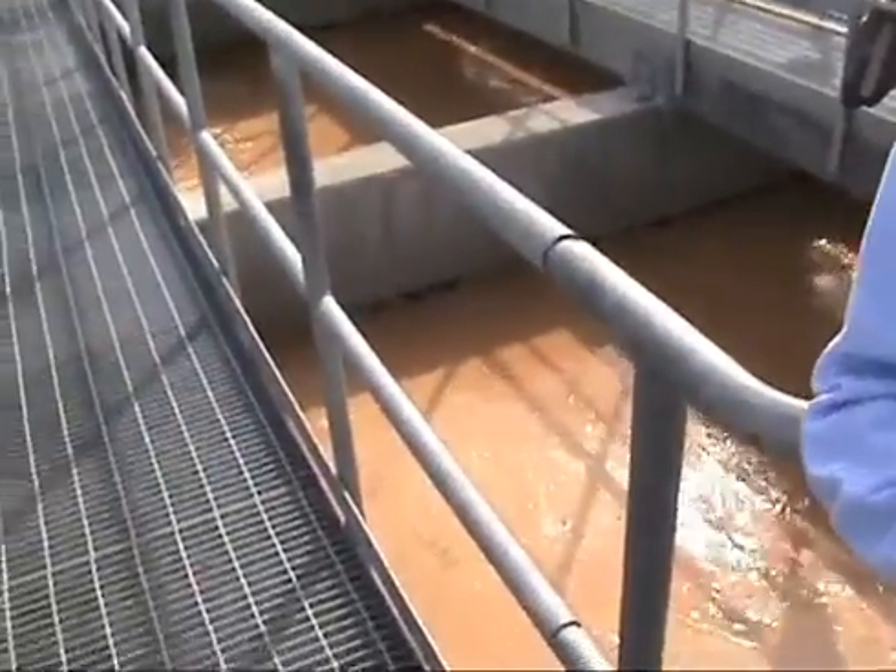And, Frank, we were talking about your ability here at the wastewater treatment plant to recycle water from the aeration basin back into the anoxic zone. Can you kind of go through that process with us? What's powerful about this treatment system is it takes the aerobic activated sludge process where we create nitrate-rich effluent — we convert all that ammonia coming in into nitrates — and we move that into an anoxic zone where in the absence of oxygen and the presence of excess BOD, additional nitrogen is consumed as the nitrates are consumed, and of course BOD is consumed. So it becomes a very powerful and efficient wastewater treatment engine, treating wastewater at a very small footprint.